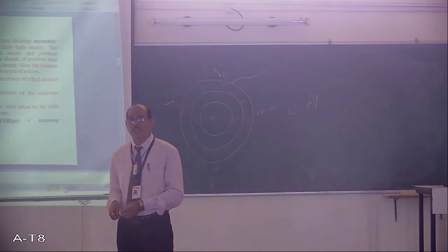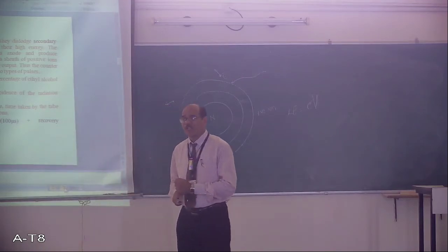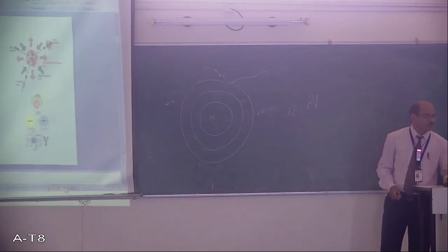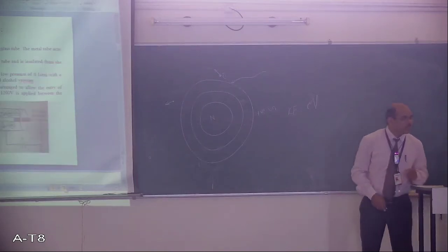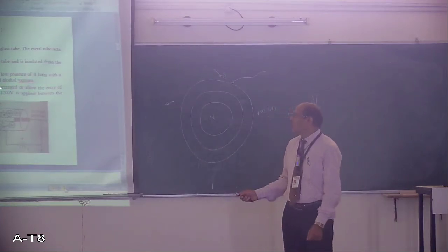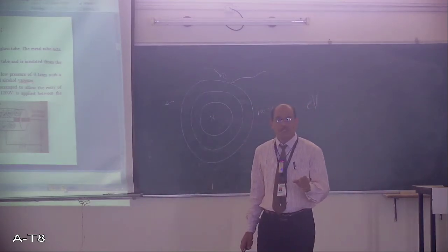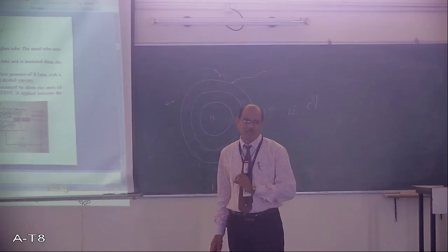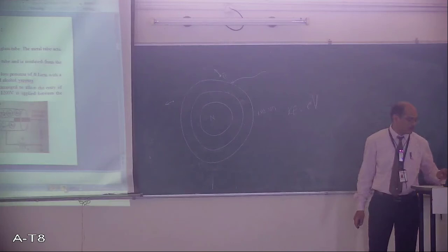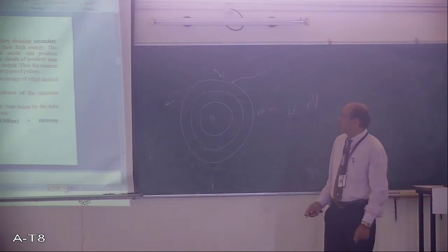Avoiding the secondary electrons is called quenching. Quenching means avoiding. So how to avoid it? As discussed earlier, 10% ethyl alcohol vapors are introduced, so that the ethyl alcohol vapors absorb the electrons dislodged from the metal surface. This will quench the generation of secondary electrons, so counts will be obtained only due to primary electrons.